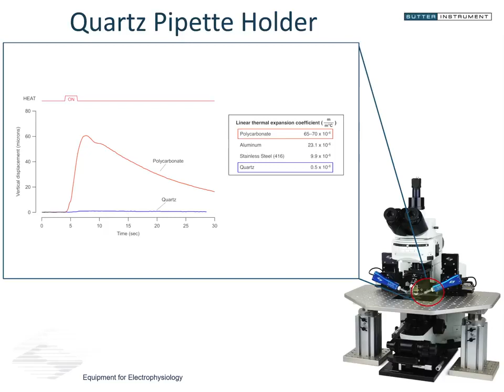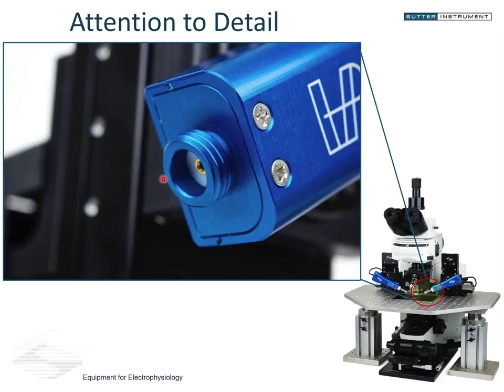So what we're looking at here is the tip of the head stage. These are the threads on the end of the head stage that the pipette holder will thread onto. It's important to note that the cap of the head stage, the Teflon connection that threads over this, if you're mounting Teflon to Teflon, this does not create a very stable surface. If you're mounting Teflon to things, generally you want to have a harder, more solid and rigid surface that it's being mated to. And in this case, we've made our head stage threads out of aluminum, and this does provide not just more stability, but it turns out also an added layer of electrical isolation. We were surprised by this, but it makes a little bit of sense that this is a sensitive spot to electrical noise pollution.